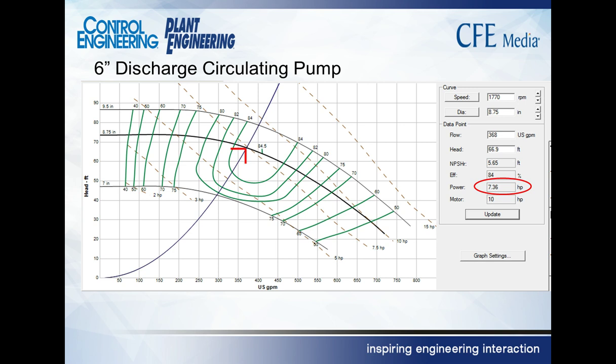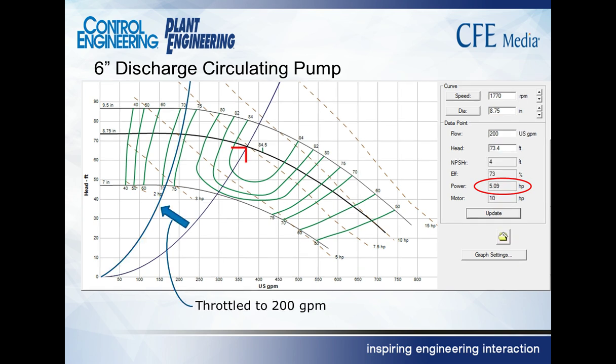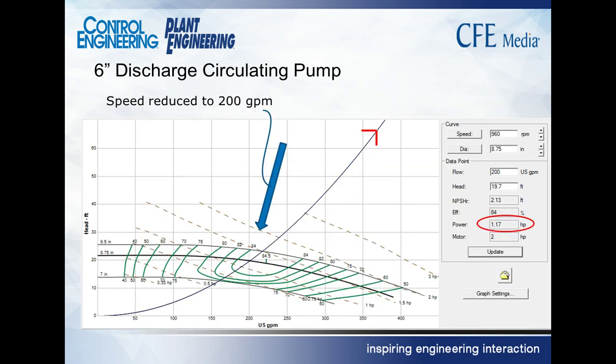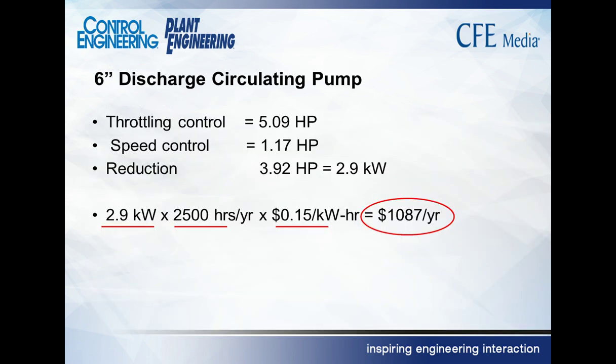Okay, a little over 7 horsepower. We closed the throttle valve. We bent that curve back, and we got it down to 5 horsepower. But instead of doing that, if we go back to the original curve, and instead we move the pump down by slowing its speed down, we bring it down to a little over 1 horsepower. Can we get that into dollars and cents?